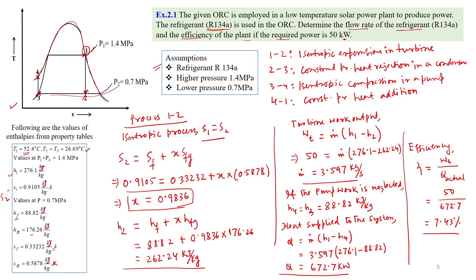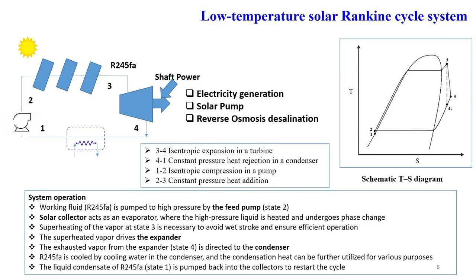This problem was chosen to help you understand how these kinds of calculations can be carried out for estimating the performance of a low temperature solar power plant. Now we can have one more configuration to produce power — with components including a feed pump, solar modules, turbine, and condenser. The T-S diagram shows: process 1 to 2 is isentropic compression in the pump, 2 to 3 is constant pressure heat addition, 3 to 4 is isentropic expansion, and 4 to 1 is constant pressure heat rejection in the condenser.